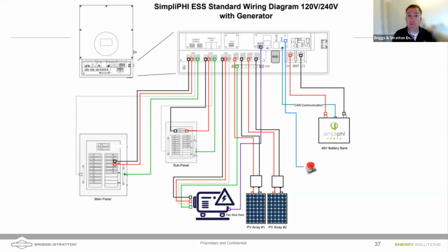We have 2 MPPT input charge controllers, so you can DC couple solar into this. We have that E-stop, and then we have the batteries on the far right. If you are going to be AC coupling in some solar to this example here, we're going to have to talk a little bit about interlocking breakers or perhaps a transfer switch to prevent, again, that generator and the solar from latching onto each other.